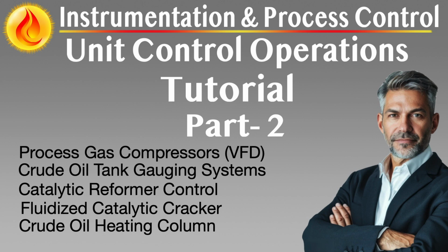Catalyst management is now an automated and adaptive process. Circulation rates, slide valve positions, and catalyst inventory are monitored and adjusted in real time based on delta P across risers, cyclone performance, and regenerator activity. Erosion-prone components like slide valves and standpipes are instrumented with vibration, wear, and temperature sensors. In some modern units, AI-driven condition monitoring predicts maintenance needs and triggers alerts for mechanical inspections before a failure occurs.